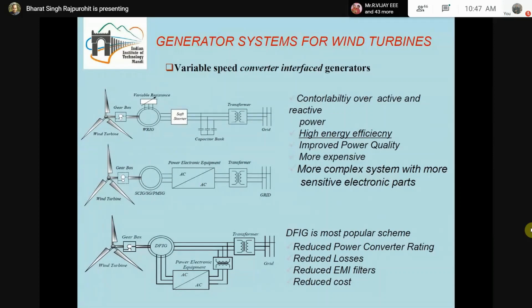Even if we are not talking about renewable energy as a wind turbine, this scheme is also used as an electric drive. The rotor side converter is utilized in very large naval ships, where these rotor side converters have a rating equivalent to the stator rating and can act as a very good electric drive. And in this case, the power processing can be double the stator power, because the stator gives a certain amount of power, and then the rotor can also give a certain amount.